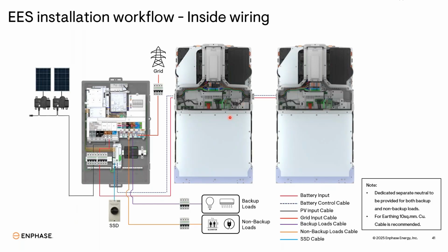And for earthing, you need 10 square mm of cable. So earthing needs to be very intact, because in your off-grid conditions, the controller will completely open it from the grid side, both line and neutral, and it will use your earthing. So your earthing needs to be intact there. So use a 10 square mm cable from battery to controller and controller to your earth pit. So use only 10 square mm copper cable there.